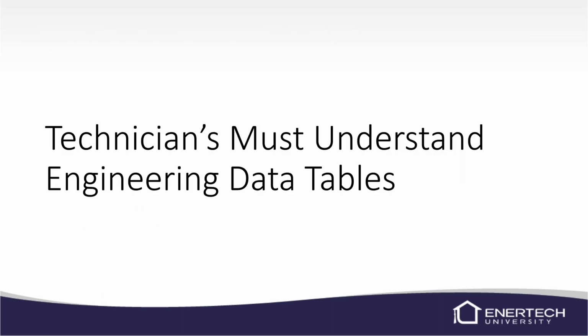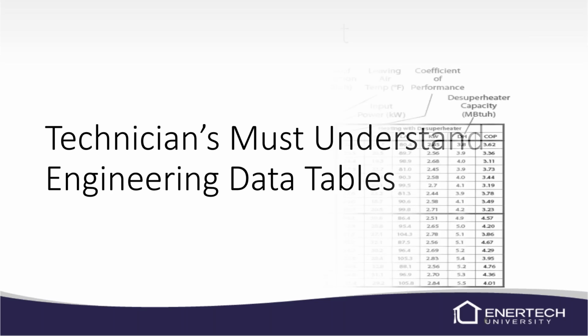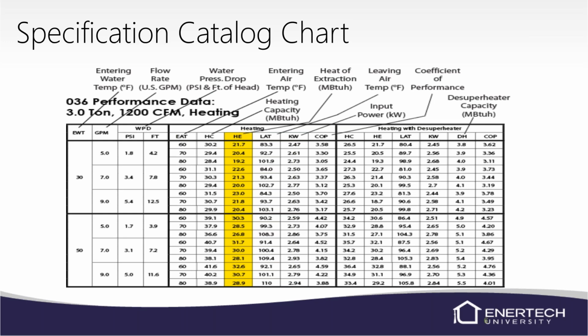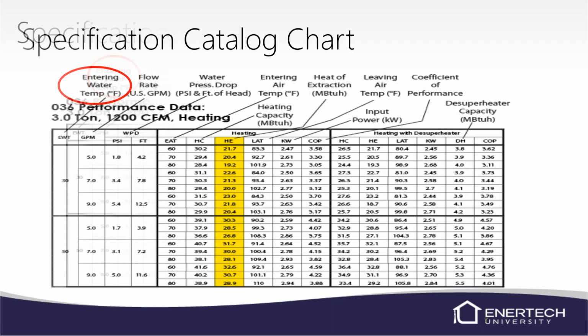So we've obviously got to understand the engineering data tables first before we really go digging into pulling out the information, because you got to understand how to read it. In our manuals, this is a spec chart from a 036, probably a packaged XT unit, more than likely. But you'll see we've got entering water temperatures, and that's just that, the water that's entering the heat exchanger on the source side. The newer manuals are a little bit better. We break it down into smaller temperature increments. On this one, it's just showing 30, 50, 70, 90 degrees.